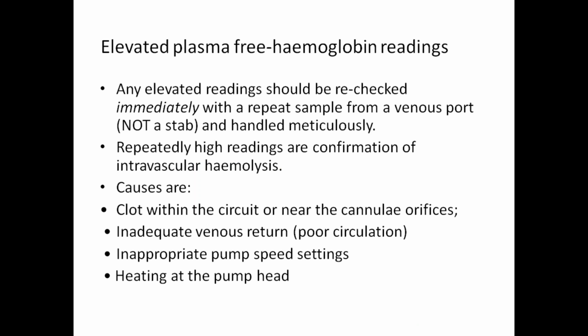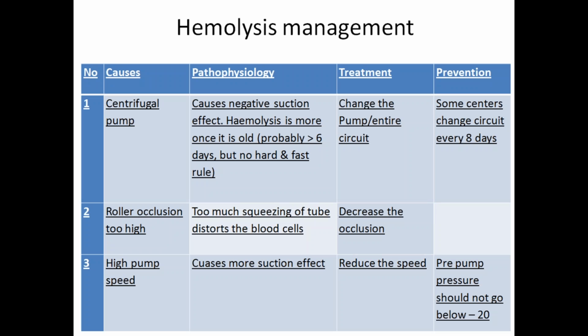If you suspect free hemoglobin in the blood, you need to be really careful how you send the sample to the lab, because free hemoglobin can be nephrotoxic. The causes could be, as I said, heating of the pump head or clots in the circuit. If you have too small a cannula or are generating too much negative pressure to get the blood, that itself can cause it. Or if you need a very high pump speed, high revolutions, to get the flows, that also can cause hemolysis. So depending on the cause, you need to go from circuit to patient and look for each and every possible reason and try to address those things.